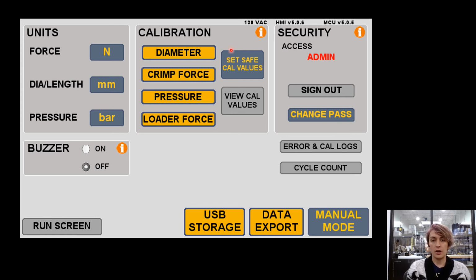Then there's the calibration box. On this machine, you can calibrate the diameter of the compression station. You can calibrate the crimping force of the compression station. You can calibrate the pressure of the clamshell gripper. And you can calibrate the loader force. This is for the auto pushrod loader attachment. There's a few other buttons here. The View Cal Values button shows you the current calibrations in the machine. And this Set Safe Cal Values is a calibration reset, sort of a factory reset button that will clear calibrations back to factory safe settings.